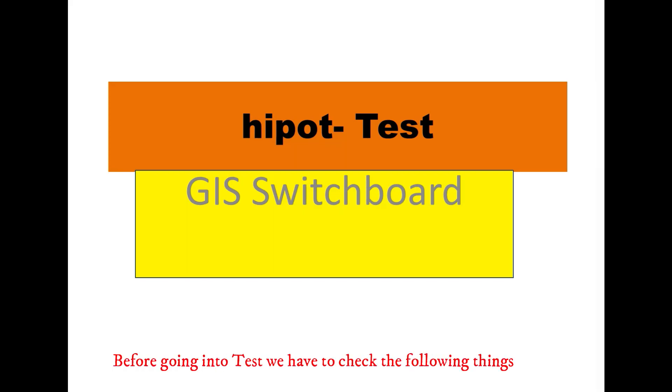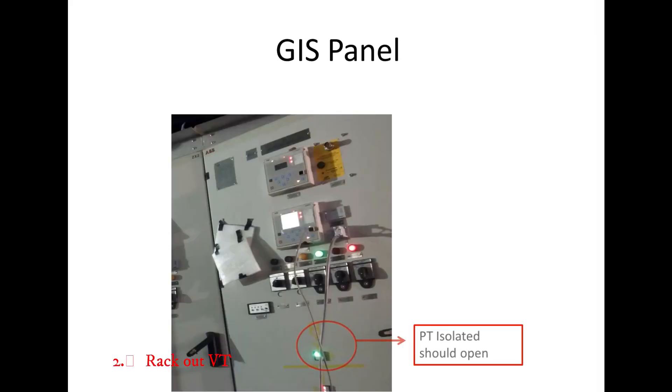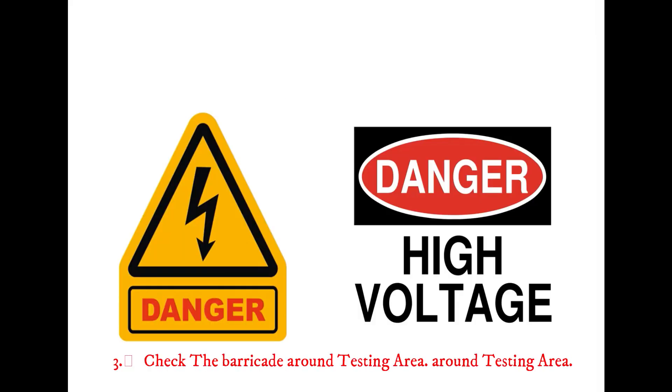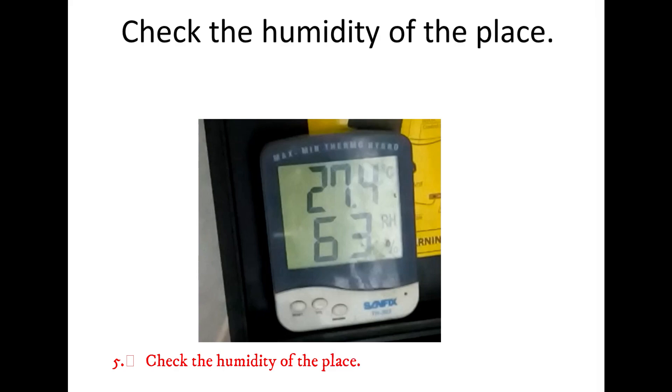Before going into testing, we have to check the following things: open air switch, rack out VT, check the barricade around the testing area. IR test has to be conducted before the Hypot test. Check the humidity of the place.